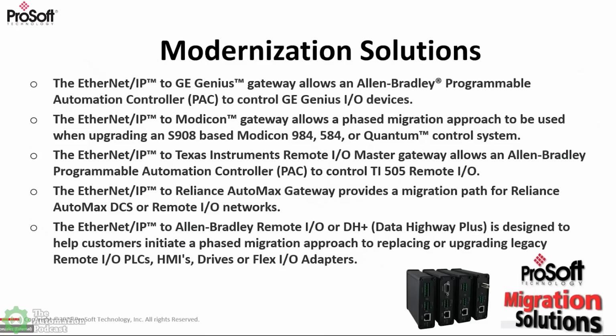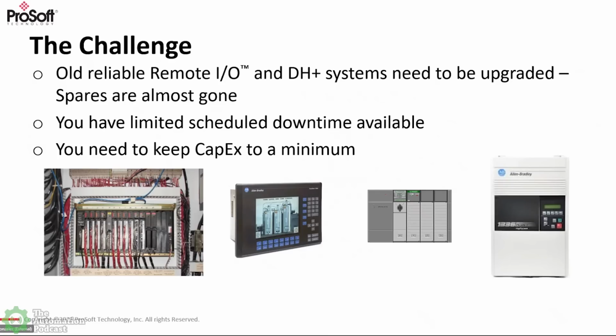How to migrate equipment using Data Highway Plus or Remote I/O. You have a Remote I/O network that is running fine, but it's comprised of older hardware that has been discontinued and parts are hard to find. Doing a rip and replace is way too expensive. Our solution enables the customer to deploy an Ethernet-based system in conjunction with the existing Remote I/O or Data Highway Plus network. This allows the user to upgrade legacy panel views, Flex I/O, drives, or even the old PLC5 processor. Upgrading your control system can now be done one node at a time, during your scheduled downtime.